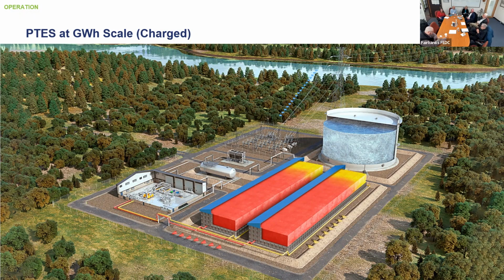There's a really interesting capture opportunity in this climate. As I said, you always have more heat than you know what to do with, and you can transfer it back in. So one of the things we've been toying around with, but haven't had time to really quantify, is the opportunity to accumulate more — we'll call it cold charge — in the cold reservoir to balance the extra heat. Because if it's sub-freezing outside, that's essentially free cold. It's a backwards way of thinking about things, but it could actually be a pretty significant impact on the performance of the system. It's just a little hard to figure out exactly how we do that yet.